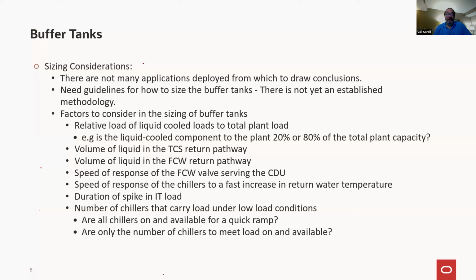And of course, the duration of the spike. I mentioned right at the beginning, you can have a spike that lasts 10 seconds, or you can have a spike that lasts an hour. And the reason that makes a big difference is if it lasts 10 seconds, there's already natural buffering in the return pathway to the plant, and you probably don't need a buffer tank, or you may have enough already.